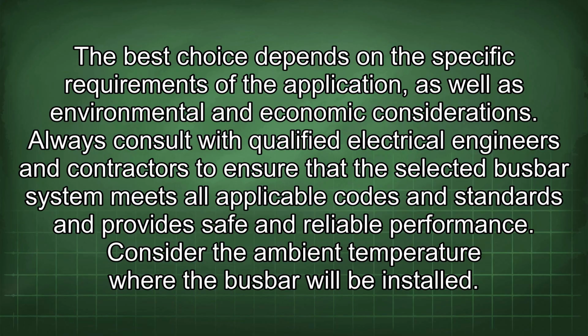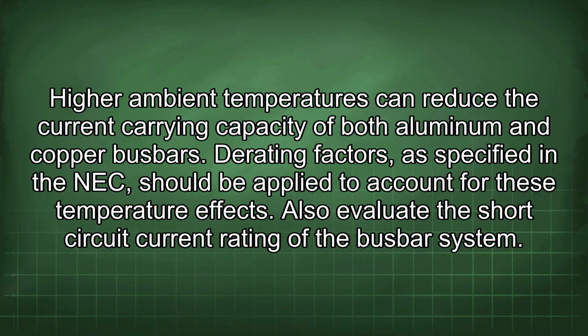Consider the ambient temperature where the busbar will be installed. Higher ambient temperatures can reduce the current carrying capacity of both aluminum and copper busbars. The derating factors, as specified in the NEC, should be applied to account for these temperature effects.